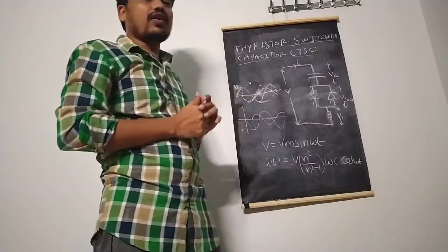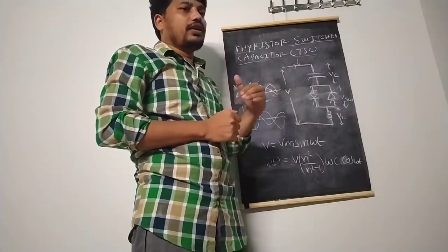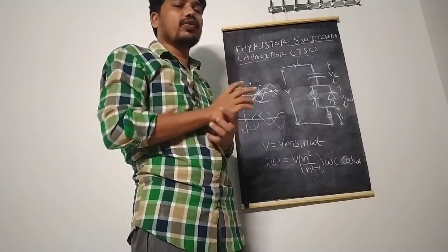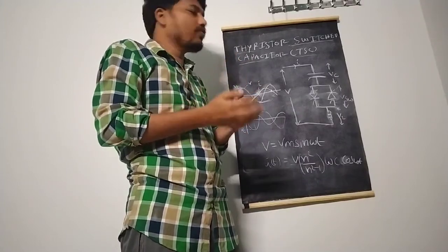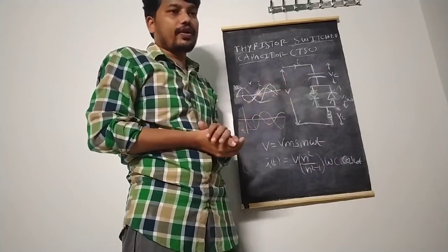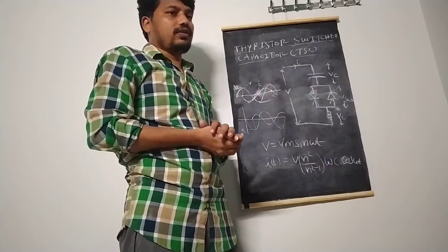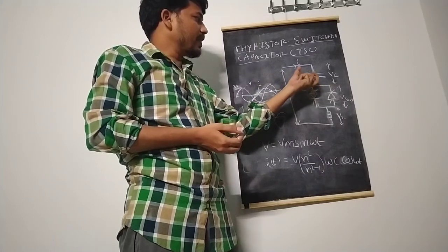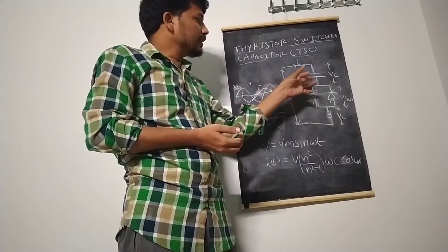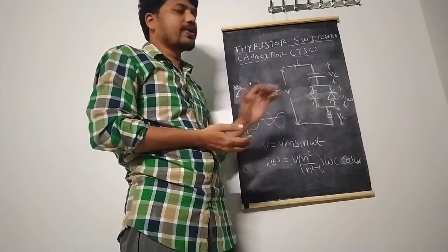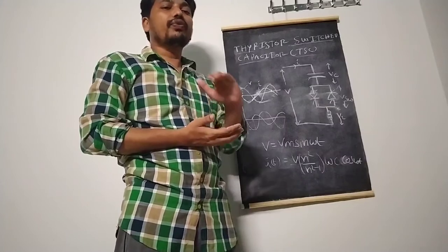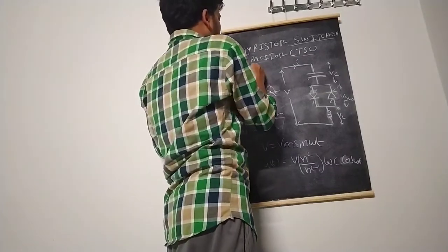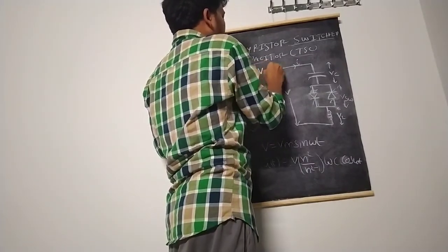The thyristor is turned on for the capacitor switching. If the turn-on or turn-off process is not done properly — without managing the residual voltage — damage might occur and the capacitor could be broken. To get transient-free operation, the system voltage V and Vc, the voltage across the capacitor, must be carefully managed.